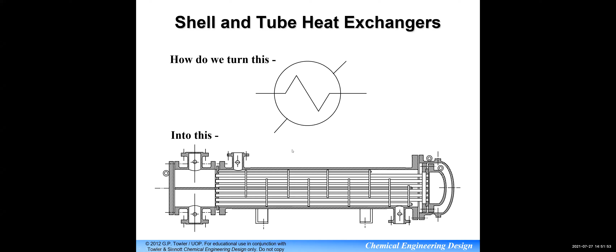We can see the figure here, and I guess you can get the understanding that if you have several channel dividers, then you can have two passes of a tube side. So this is your first pass, and then goes here, you have another divider, and then you go there, and this is your second pass, and this is the third pass, and this is your fourth pass of your tube. So you can have a 4 pass of tube sides and a single pass on the shell side. So only one pass like that, even though you have the so-called baffle.